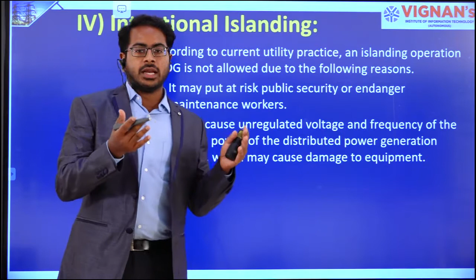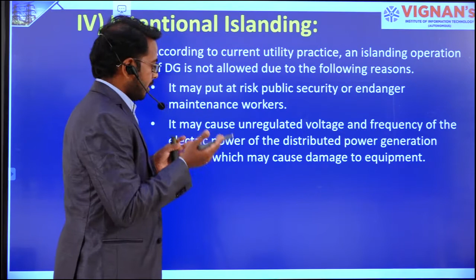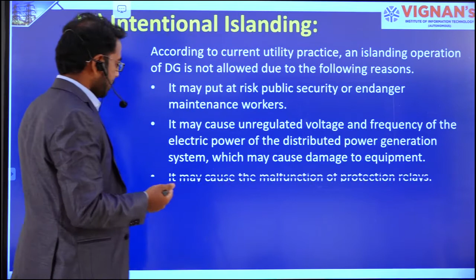It may cause unregulated voltage and frequency in the distributed power generation system, which may cause damage to equipment. Because of the sudden islanding of DG, the grid is suddenly disconnected from the DG. What will happen? It damages the equipment. Voltage fluctuations or frequency fluctuations will be there, and it may cause malfunction of protection relays.